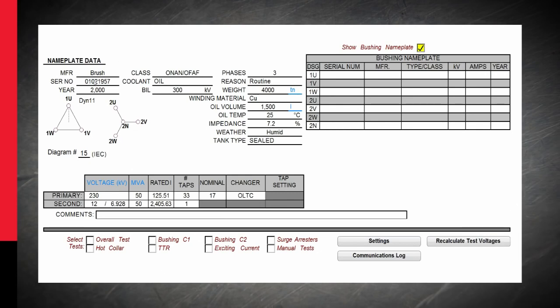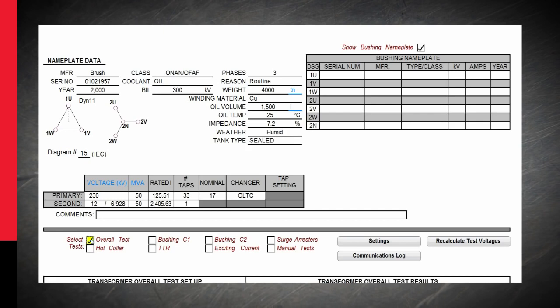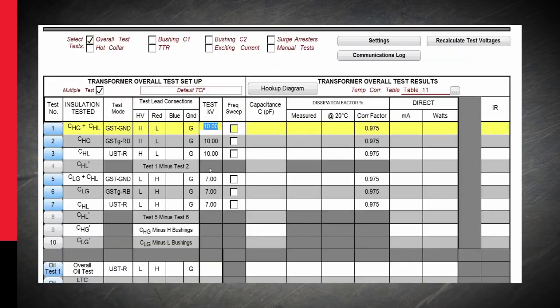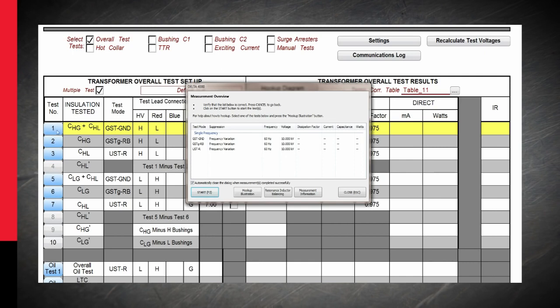We are now required to fill in nameplate information on our two-winding transformer form. This includes critical information such as oil temperature, required to evaluate test results. Next, we check off our overall test. We ensure that the proper test voltages are set for both high side and low side testing. Once properly set, we depress the test button and test sequence will begin.